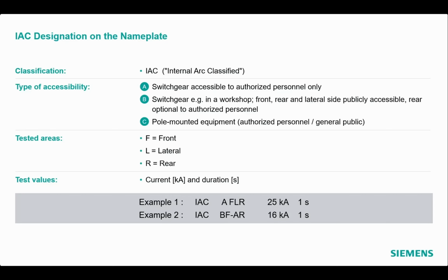The switchgears that are accessible to authorized personnel only have Type A designation. On the other hand, the switchgears that are accessible to the public are designated with Type B. The pole-mounted equipment is designated with Type C and are accessible to authorized personnel as well as general public upon satisfying appropriate requirements.